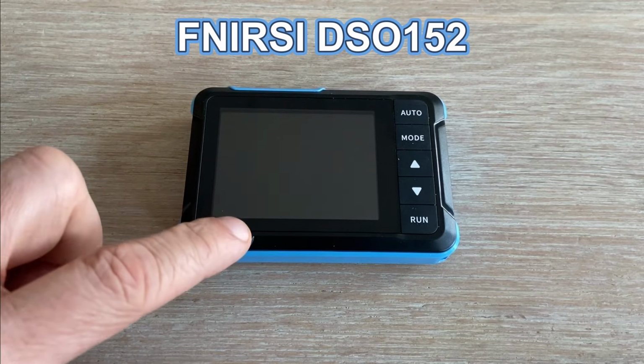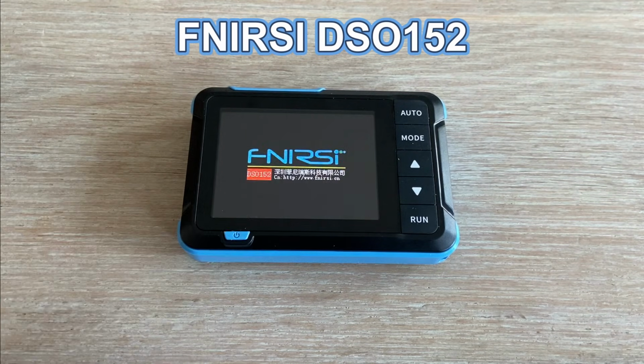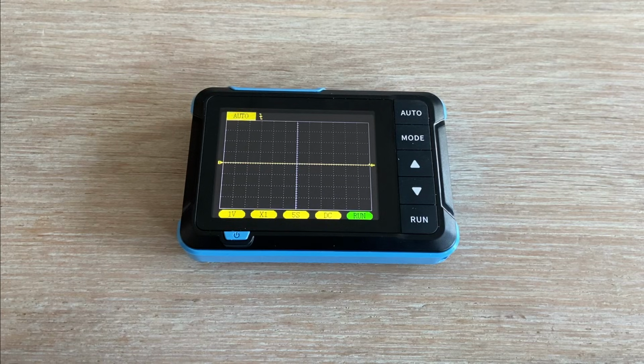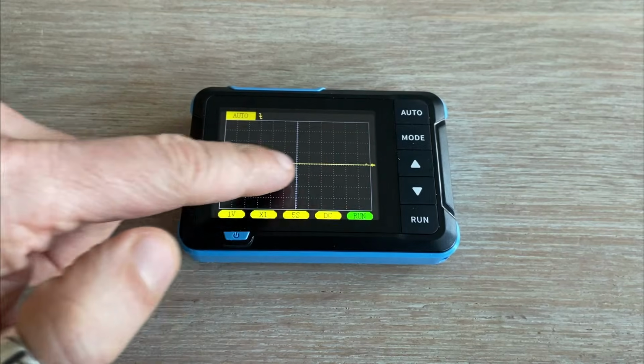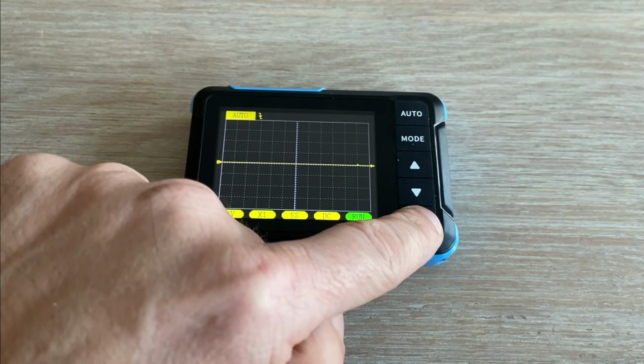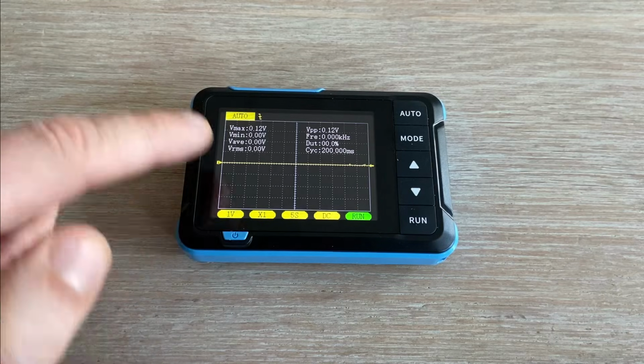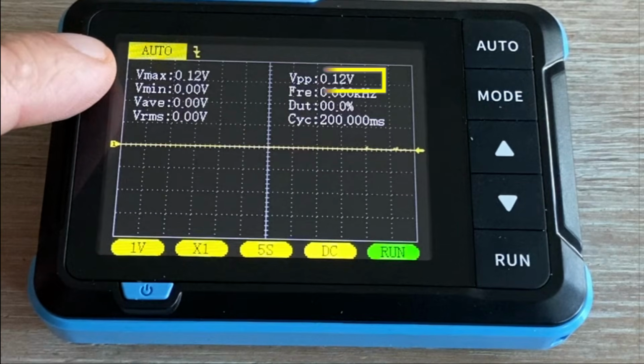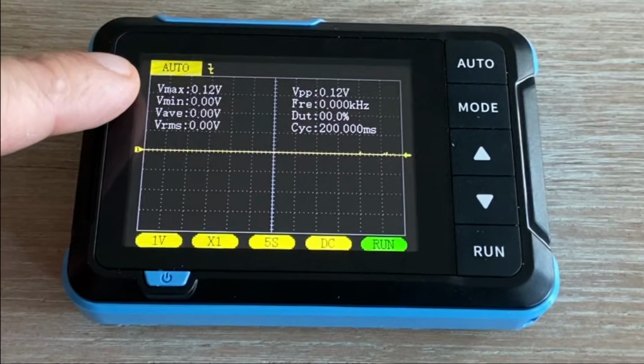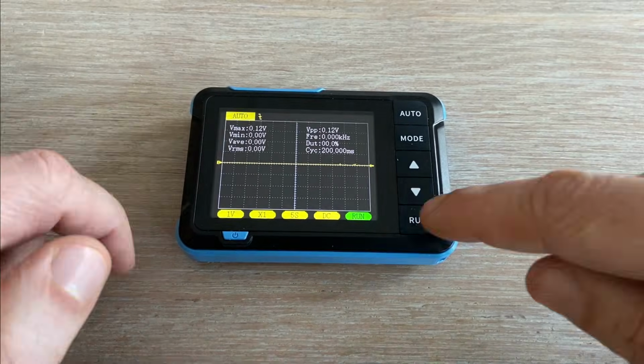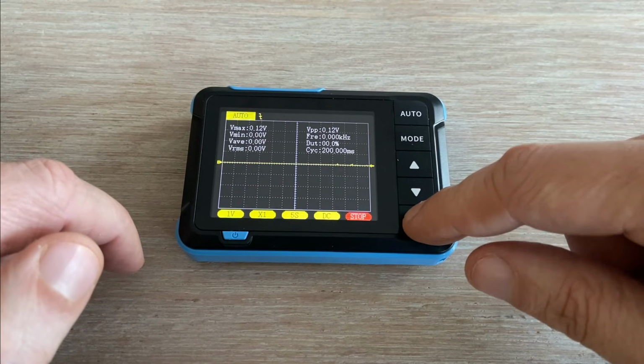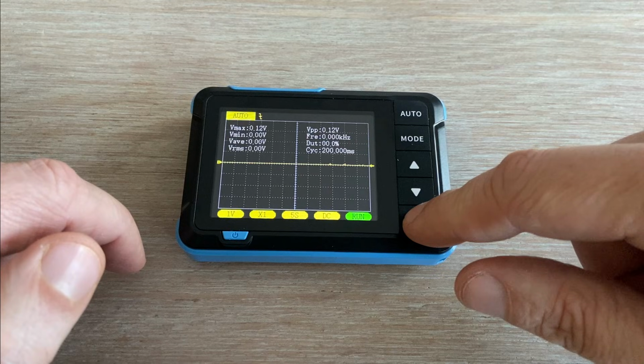Let's take a closer look at this device and power it on. The background grid is a typical oscilloscope time-voltage grid. Horizontal spacing represents the time per division. Vertical spacing represents the voltage per division. Here's the time axis. By pressing and holding the run button briefly, you can display the parameters of the incoming signal. The oscilloscope shows the signal's peak-to-peak voltage, maximum and minimum levels, frequency and more. At any time you can take a snapshot of the signal for analysis by short pressing the run button. Pressing run again resumes capturing the signal in real time.